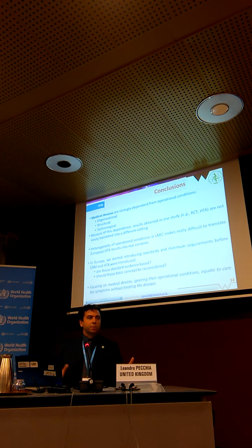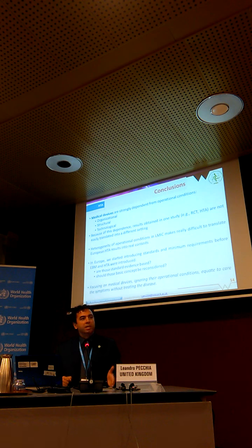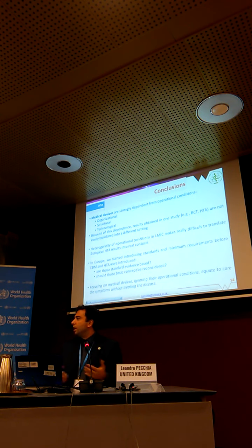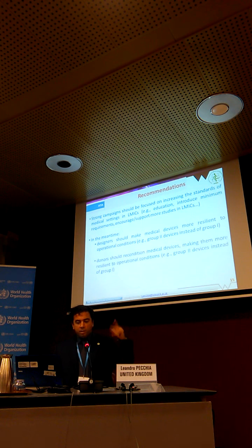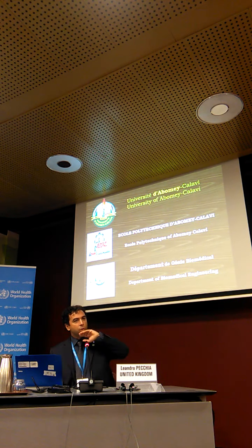Our recommendation is that, while we hope low-income countries will eventually have the same hospital infrastructure we have in Europe, in the meantime we should design more resilient medical devices. We should recondition devices that we donate, making them more resilient to power instability, to varying user levels, and to the community environment. That is something I do not see enough discussion about, and that is why I wanted to bring it to this table.